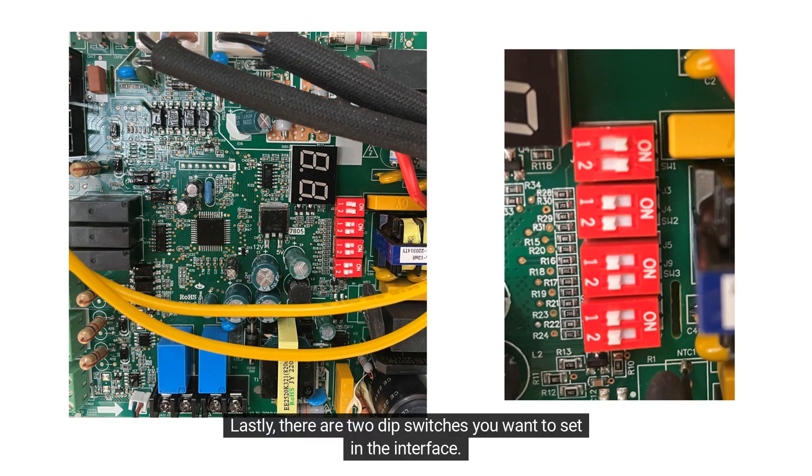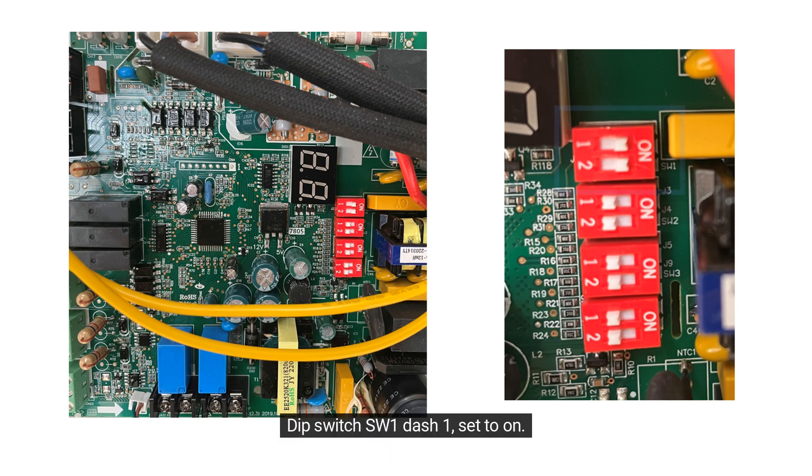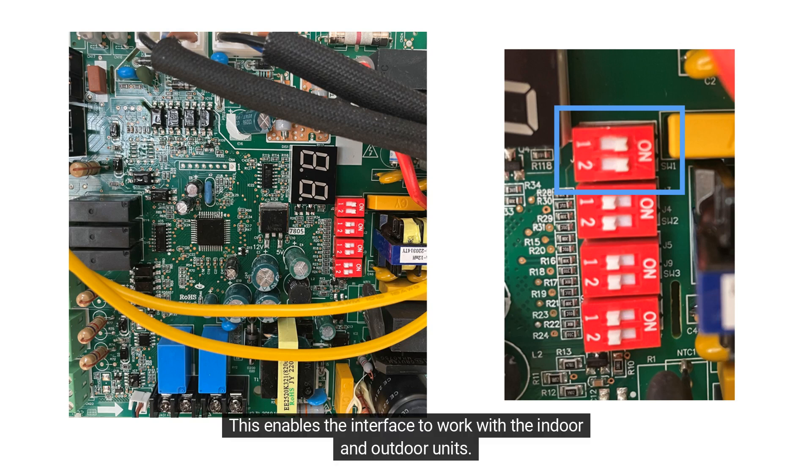Lastly, there are two DIP switches you want to set in the interface. Set DIP switch SW1-1 to ON — this turns on the LED display. Set DIP switch SW1-2 to ON as well — this enables the interface to work with the indoor and outdoor units.